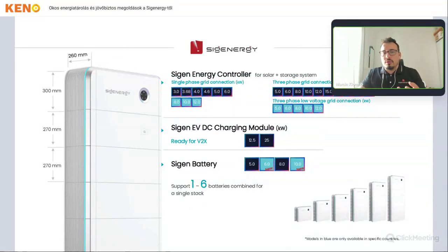Right now, from different battery kinds, the first product was delivered at 280 ampere hours, 9 batteries, which gives us exactly 8 kilowatt hours of usable capacity. Right now the market trend is to change the cells towards 314 ampere hours, so generally one cell is 1 kilowatt hour.